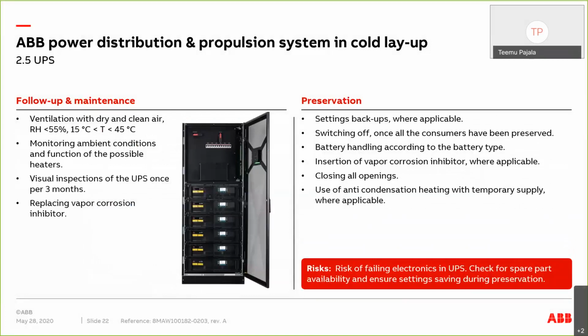The UPS is also an electronic system, so the same considerations apply there. Temperature within the limits and humidity at an acceptable level. And again, vapor corrosion inhibitors need to be replaced when it's time. And otherwise, visual inspection once per 3 months. And for preservation, again, backups of all the software and parameters where applicable, of course. And then after all the equipment this UPS is supplying has been switched off, the UPS itself can be switched off.